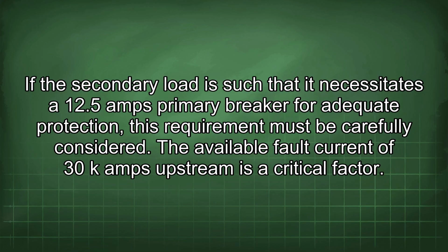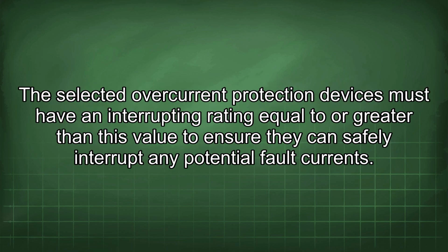be carefully considered. The available fault current of 30 kA upstream is a critical factor. The selected overcurrent protection devices must have an interrupting rating equal to or greater than this value to ensure they can safely interrupt any potential fault currents.